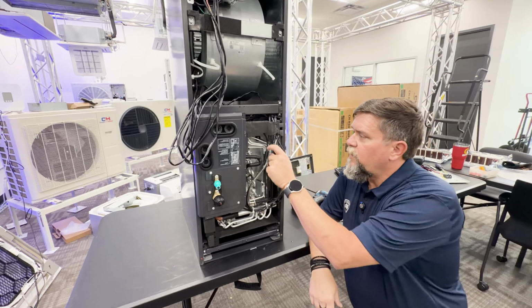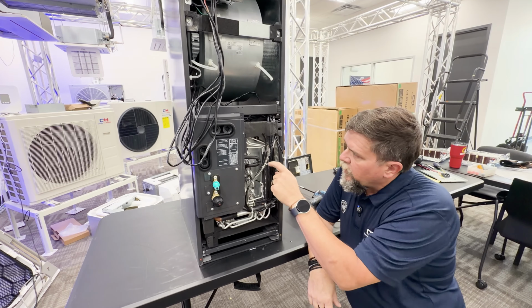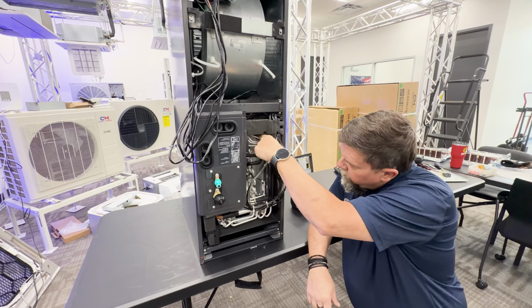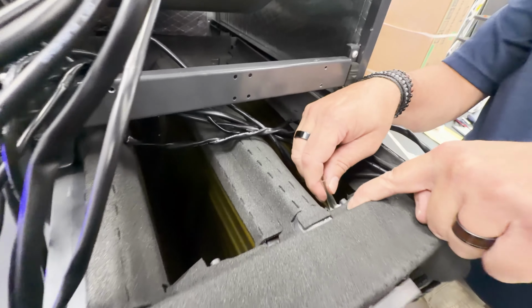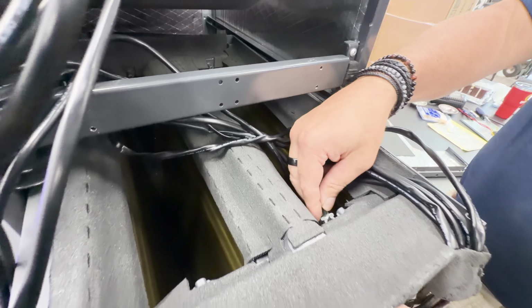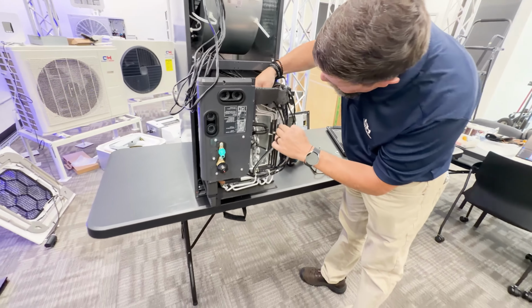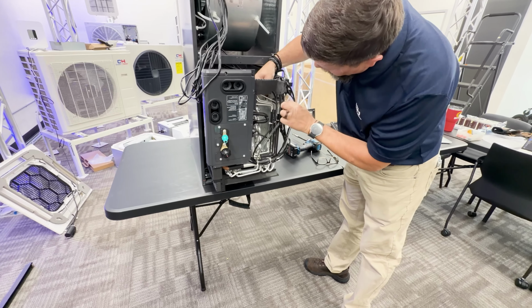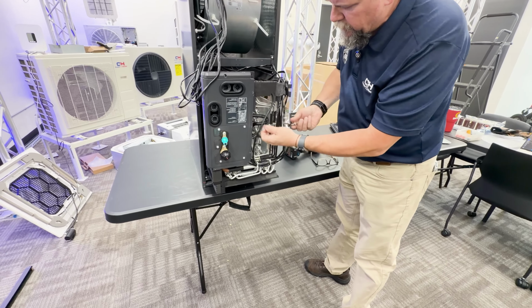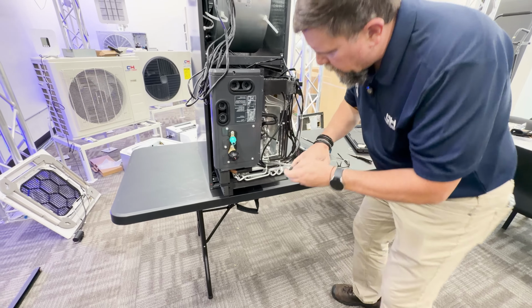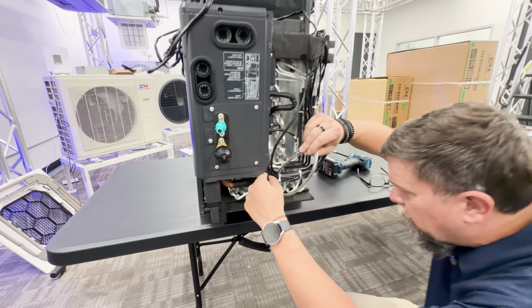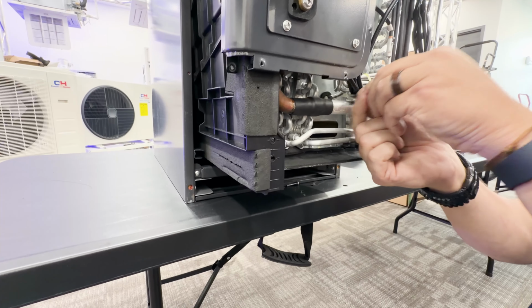Next step is that we need to relocate the room air thermistor. When you look at the coil, you'll see up here there's a grommet. Take a look underneath the coil here, it's on a clip. We'll remove it from the clip, and then we can pull the thermistor out through the grommet, and relocate it in the hole down below.